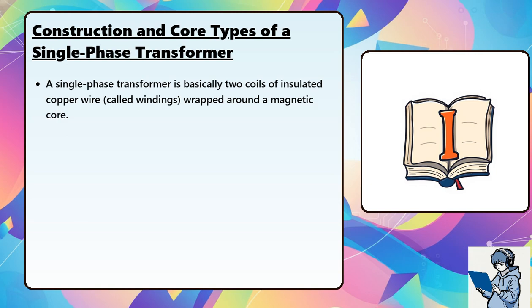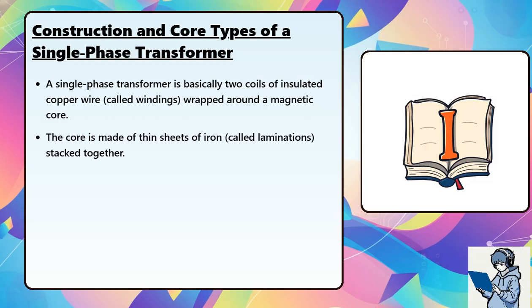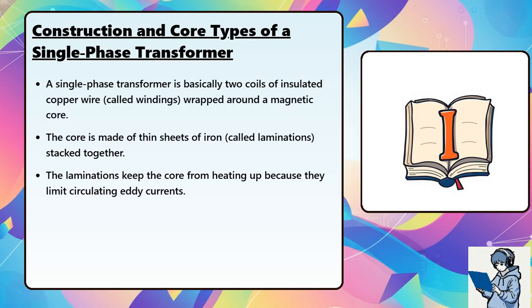A single-phase transformer is basically two coils of insulated copper wire, called windings, wrapped around a magnetic core. The core is made of thin sheets of iron called laminations stacked together. The laminations keep the core from heating up because they limit circulating eddy currents.